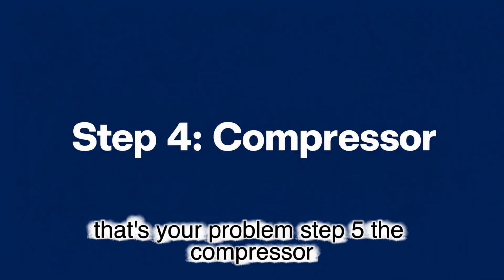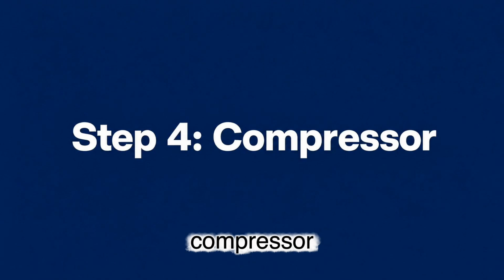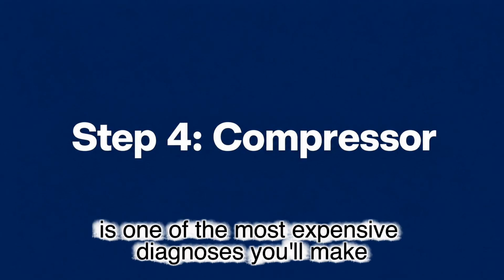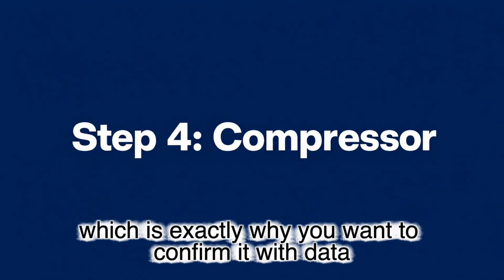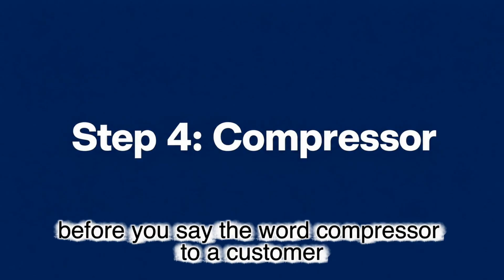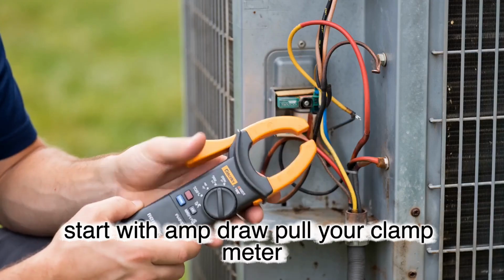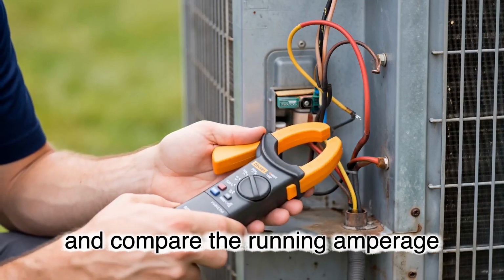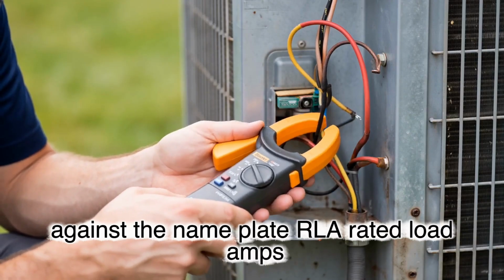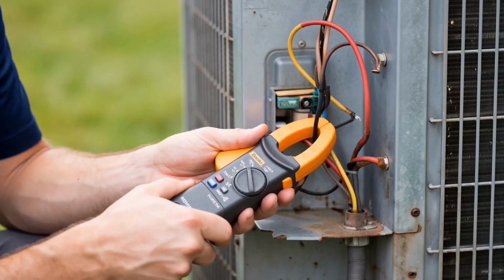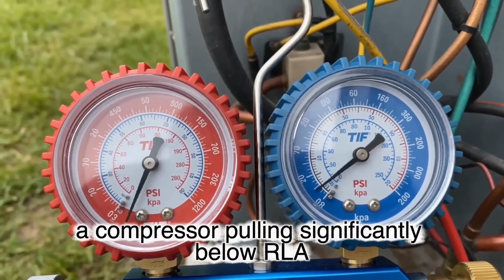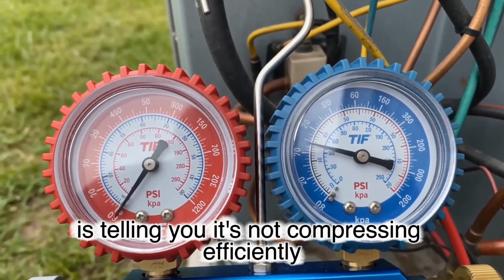Step 4, the compressor. A weak or failing compressor is one of the most expensive diagnoses you'll make, which is exactly why you want to confirm it with data before you say the word compressor to a customer. Start with amp draw. Pull your clamp meter and compare the running amperage against the nameplate RLA, rated load amps. A compressor pulling significantly below RLA while pressures are off is telling you it's not compressing efficiently.